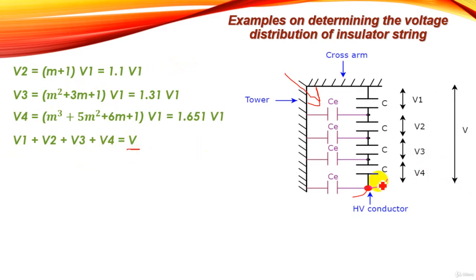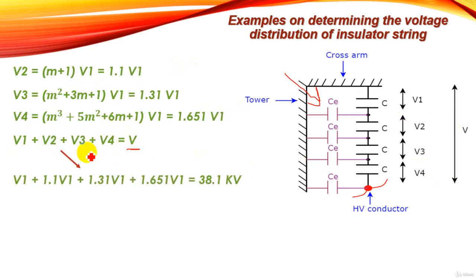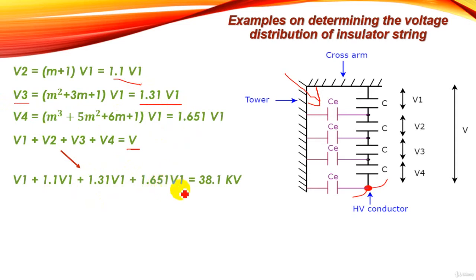The fourth equation is V1 + V2 + V3 + V4 equals the total voltage V of the insulator string. Substituting: V1 + 1.1·V1 + 1.31·V1 + 1.651·V1 equals 38.1 kV. So we have four equations in four unknowns and can solve for V1, V2, V3, and V4.